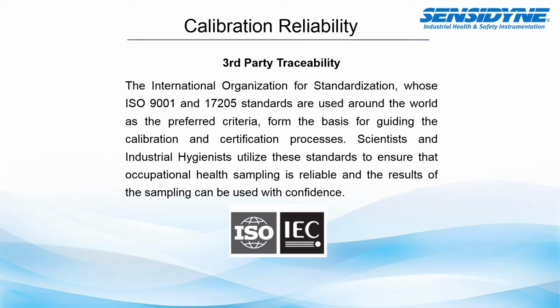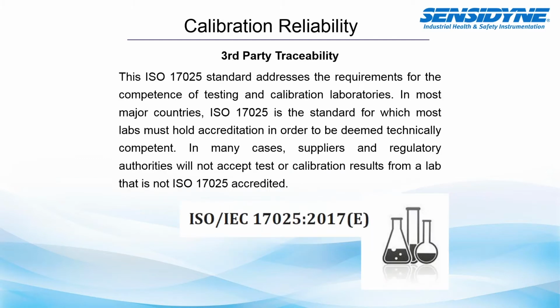Now, the International Organization for Standardization, ISO 9001 and ISO 17025, are used around the world as the preferred criteria to form the basis for guiding calibration and certification processes. Scientists and IHs use these standards to ensure the occupational health sampling is both reliable and the results can be used with confidence. The ISO 17025 standard addresses the requirements for specific competence of testing and calibration laboratories, and in most major countries, the ISO 17025 standard is required for laboratory certification in order to be deemed technically competent.